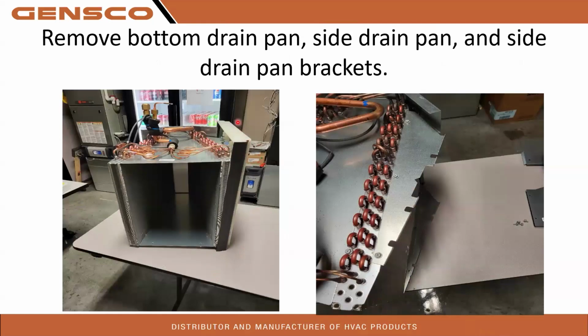And you're going to remove this horizontal right drain pan. So the bottom pan has to come off in order to get this off. Otherwise, you're going to end up breaking the pans because this thing does sit inside your bottom drain pan. So bottom drain pan must come off before this side panel comes off. Once you get that off, this drain pan will just fall right out. No screws or anything holding it in at that point.